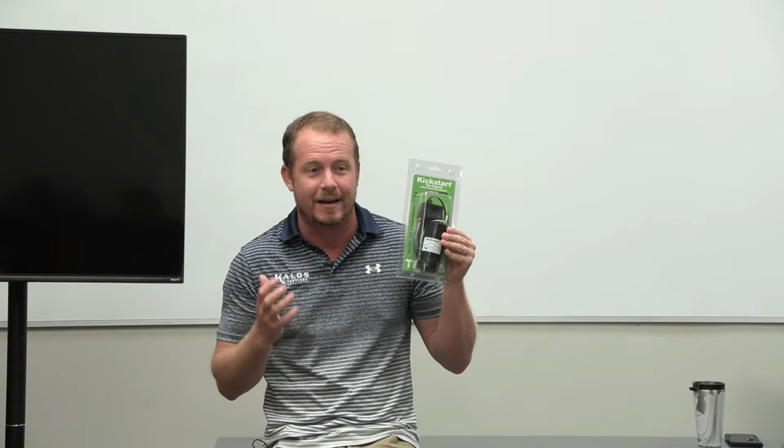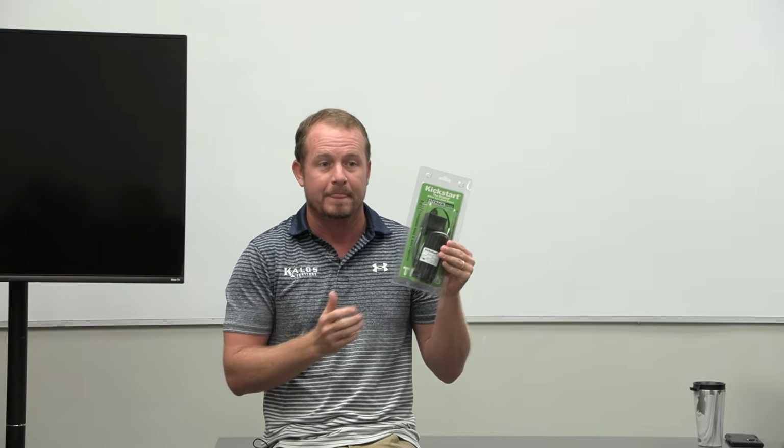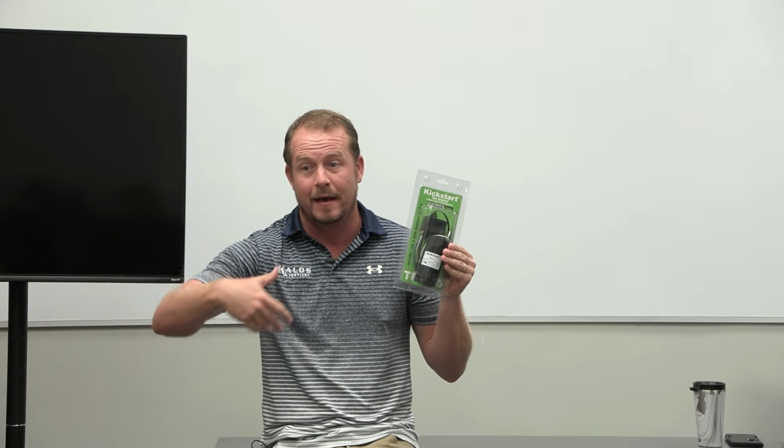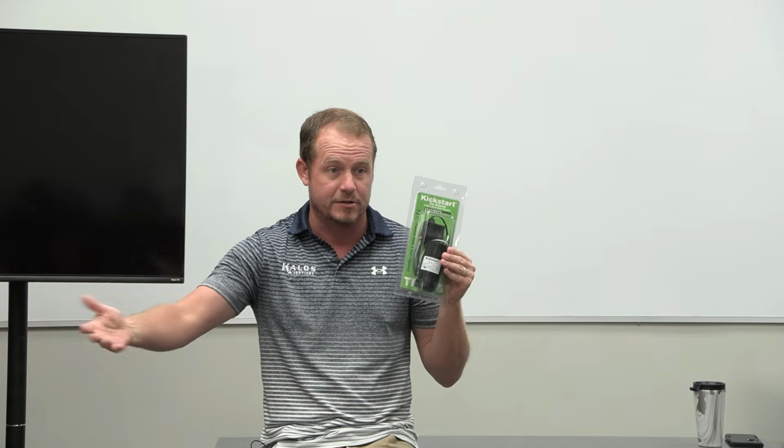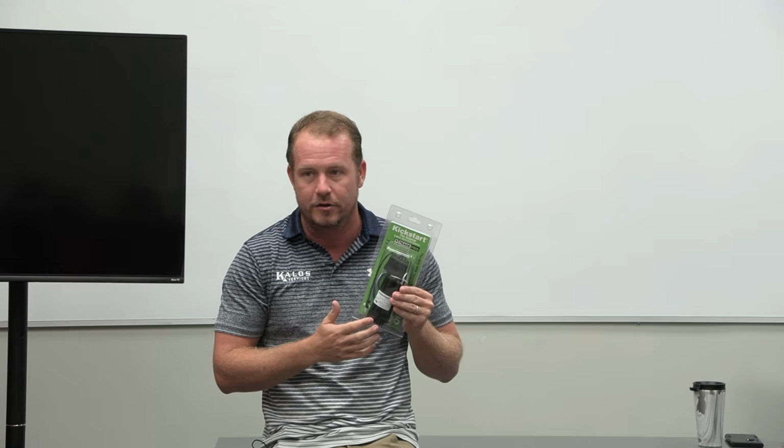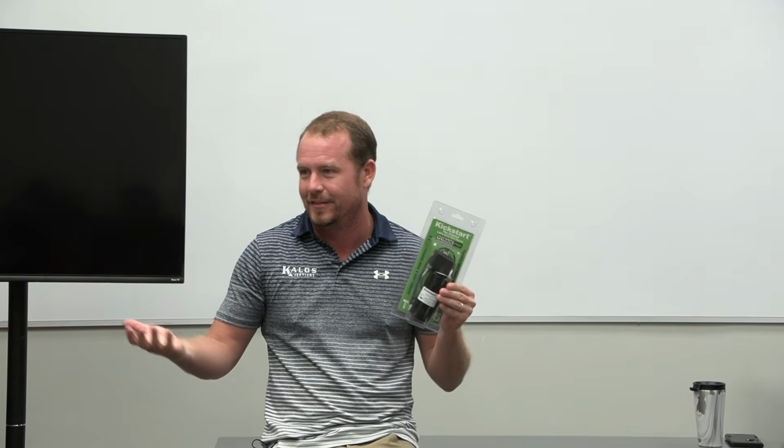But let's say this relay is set up so that rather than taking it out at 80% of the motor speed, it waits until it gets to 95%. That means it's staying in too long, and the start winding is getting hotter than it should. It's not good for the compressor. Now let's say, to be safe, they take it out early, which is what they tend to do because they don't want to overdo it. Well, now they underdo it. So it takes it out at 70% of motor speed rather than 80%, and now it's not as likely to keep starting consistently.